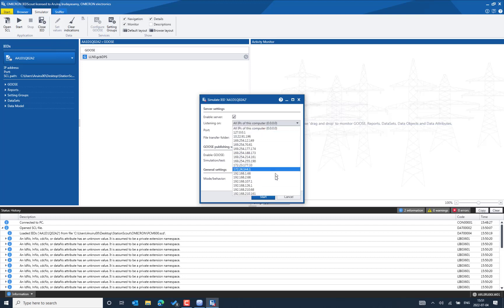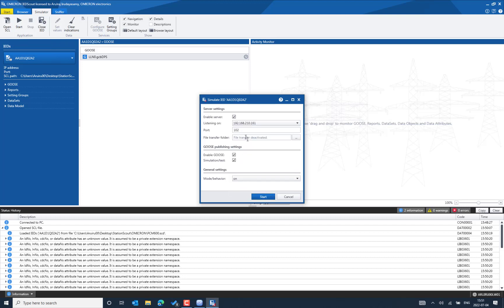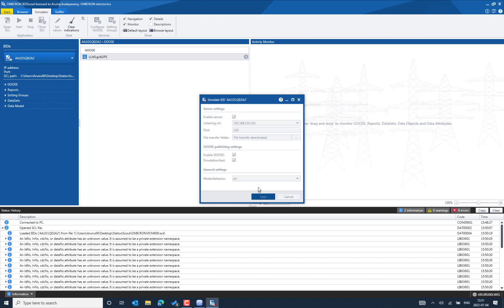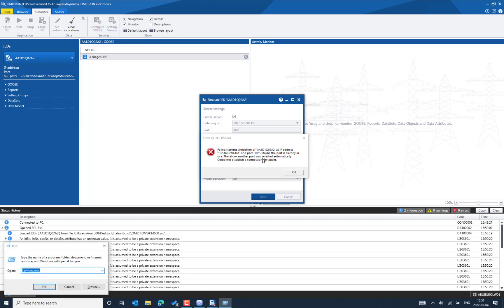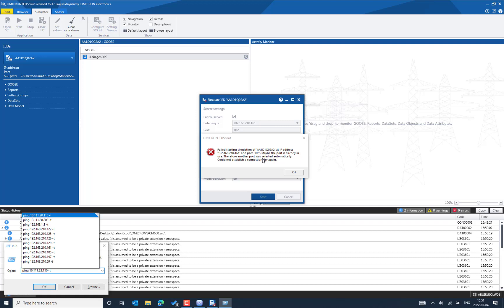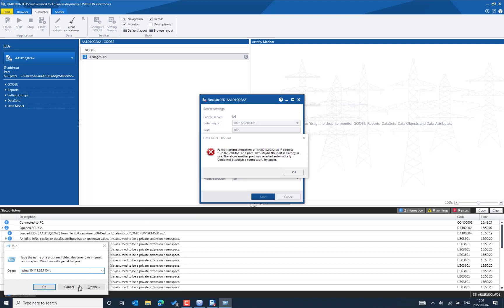There we can see the IP address we need to simulate exactly. You can also uncheck the simulation flag for the GOOSE message in case you are in a test environment or if you know what it will create in the real environment. By default we use port 102 for the simulation of the MMS server. When trying to start the simulation, we see that the IP address or port may be in use on our network. We have already added the IP address on the adapter, so that is fine.